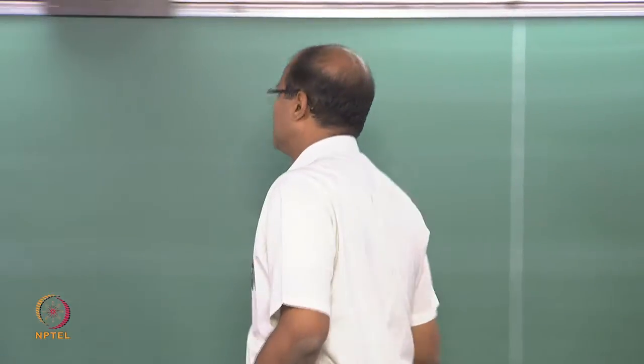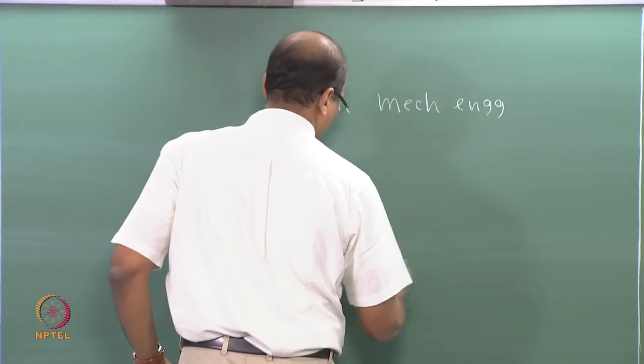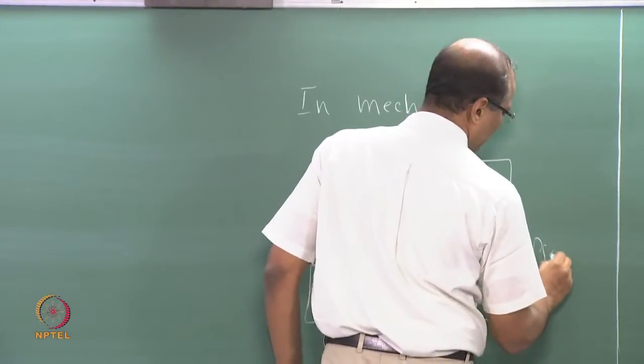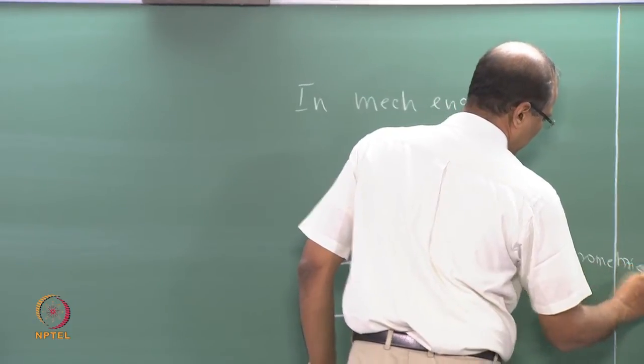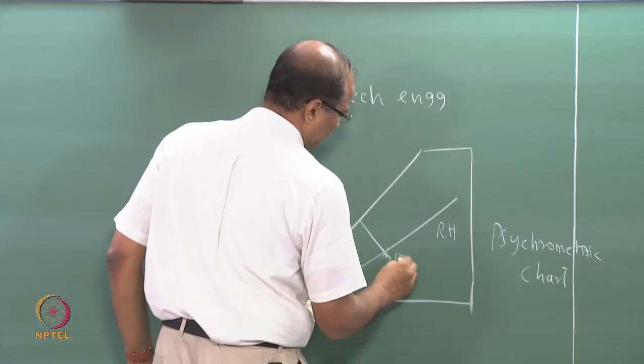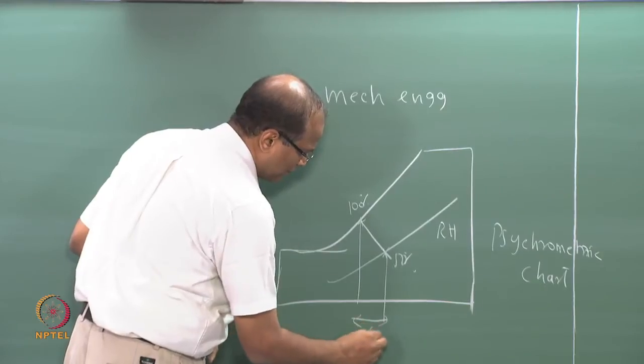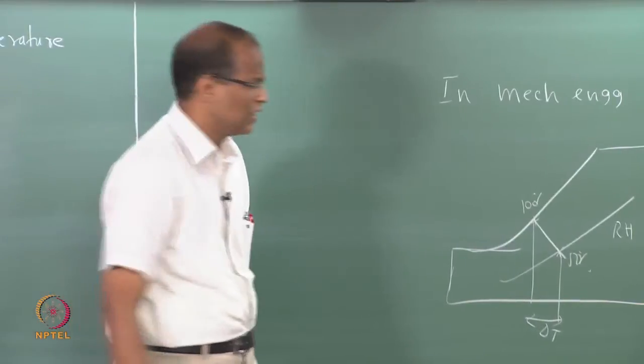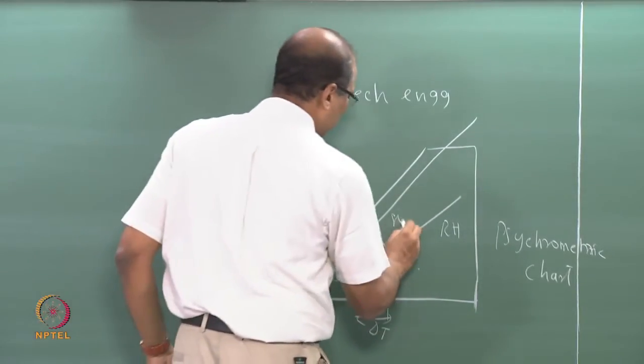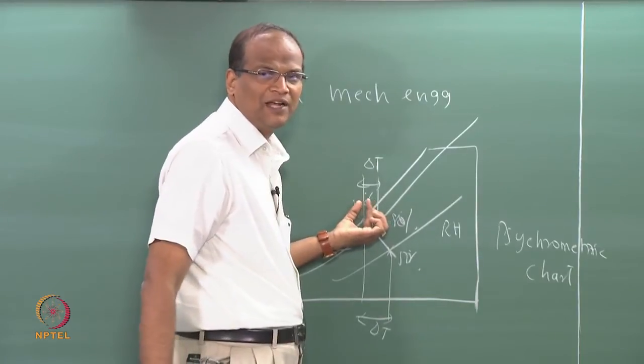For example, in mechanical engineering we have a psychrometric chart. This is some RH. Let us say from RH 50% to 100% — if it goes, this is the cooling which is possible. If you consider a situation like Chennai, we saw already that what was the RH yesterday — 79, it is already 80% here. So you will get very little cooling. If the relative humidity is very high, the delta T you get by adiabatic saturation is very low.